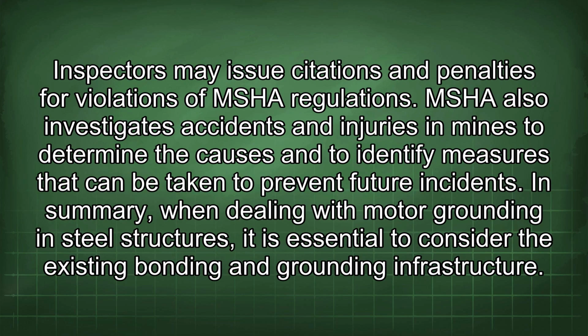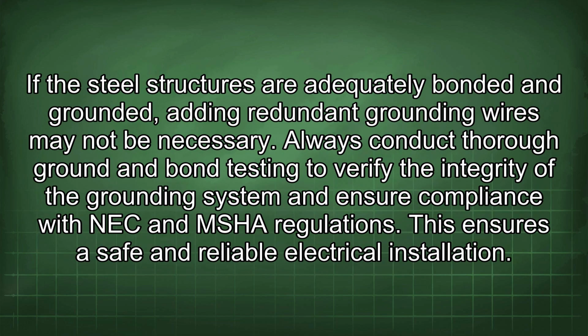Inspectors may issue citations and penalties for violations of MSHA regulations. MSHA also investigates accidents and injuries in mines to determine the causes and to identify measures that can be taken to prevent future incidents. In summary, when dealing with motor grounding in steel structures, it is essential to consider the existing bonding and grounding infrastructure. If the steel structures are adequately bonded and grounded, adding redundant grounding wires may not be necessary. Always conduct thorough ground and bond testing to verify the integrity of the grounding system and ensure compliance with NEC and MSHA regulations. This ensures a safe and reliable electrical installation.